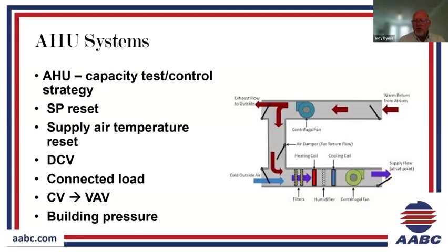And so then we want to get the coil capacity, so the heating and cooling coils. If they're water, we're going to get the entering and leaving water temperature and water flow. We're going to get entering and leaving air temperature across each coil to determine the capacity of that coil. And so what we start thinking about and contemplating as we're going through these systems and observing them is, what is the capacity? What's the control strategy? How are we controlling that unit to achieve the desired leaving air conditions?